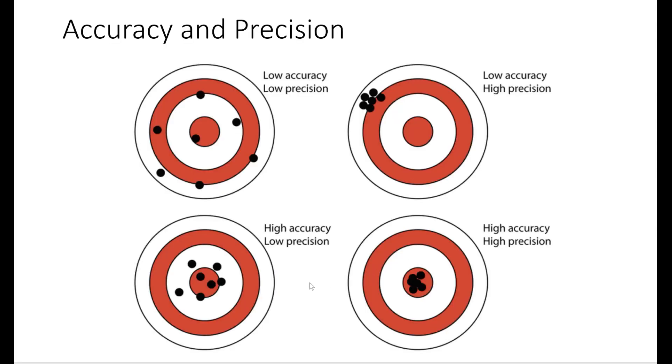So what does this mean for the POP2? Well, the accuracy is very good. The mean values are almost zero, so it's right on target, and the precision or the standard deviation is less than 0.1 millimeter. So we're somewhere between here and here.